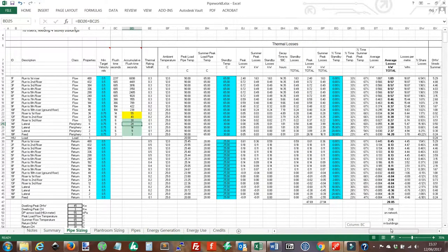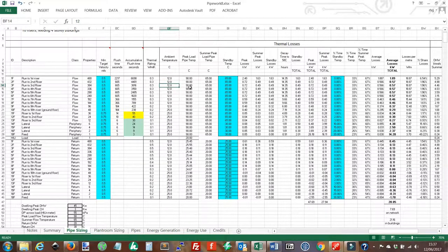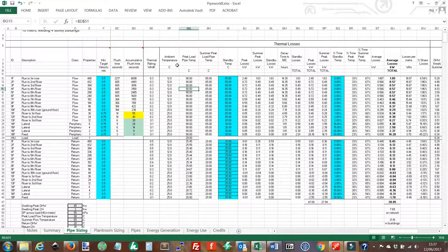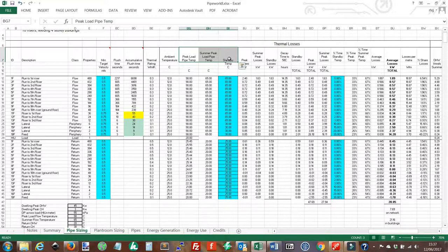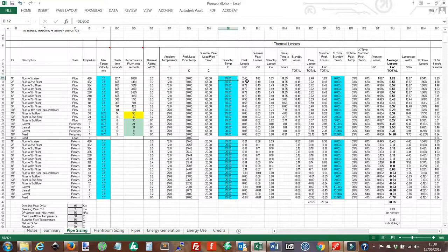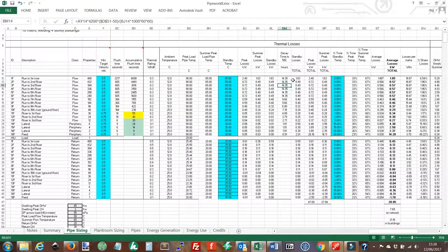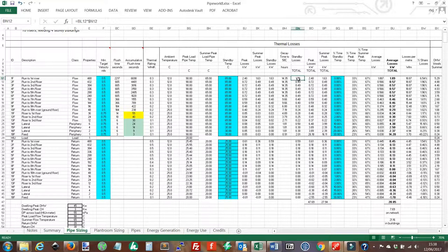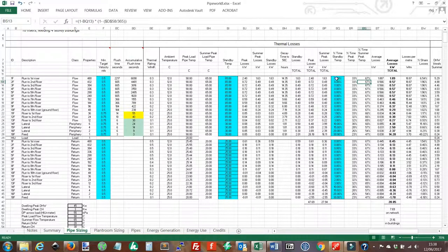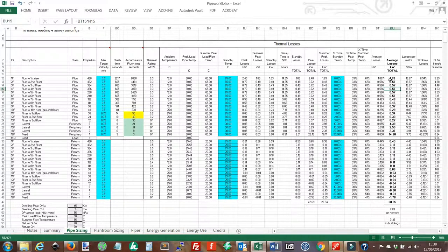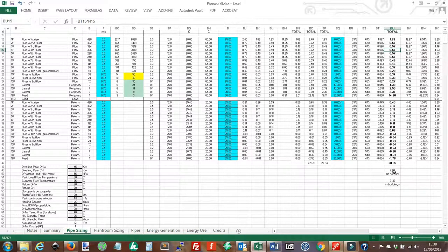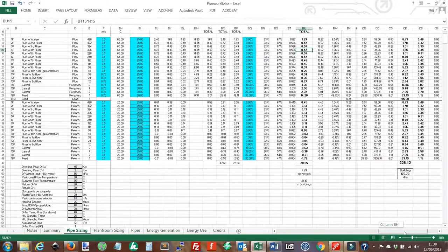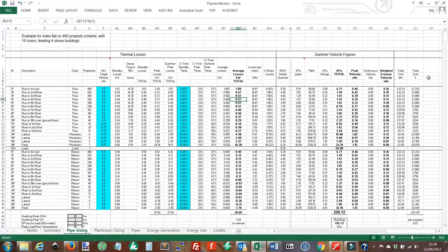Moving on to thermal losses. We have a rating which comes from the pipe work chart. Ambient temperature. Then to work out the actual losses we split the system into three modes of operation: peak load in winter, peak load in summer, and standby mode. We have the temperatures during each of these modes of operations, the calculated heat losses. We have a decay time. So this just tells us how long it takes for the pipe to cool down to 50C. We can work out the total losses across the whole network. And then from these three here which tell us the percentage of time spent in each mode, we can work out the average total heat losses for those pipes across the network. And these add up here to give us the losses on the network and in buildings. This is repeated for summer. And then we have two columns doing our costings.